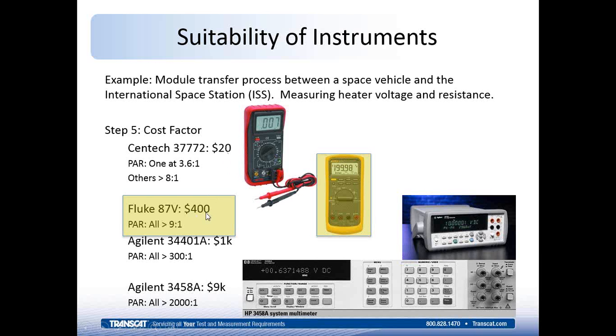And so if you're thinking about other applications, especially for a handheld multimeter, you might want to go with the Fluke 87 because it's going to have tighter tolerances for its application and for its use in other applications in the production plant or in the field or for testing. But that's certainly something that should be taken into consideration in addition to this particular application, and does it meet what it needs for that application.